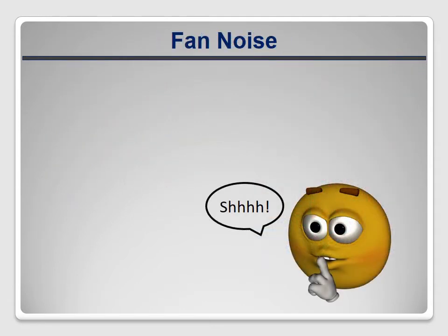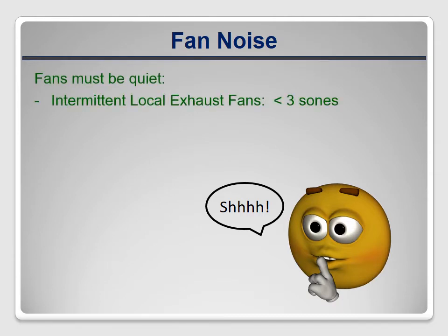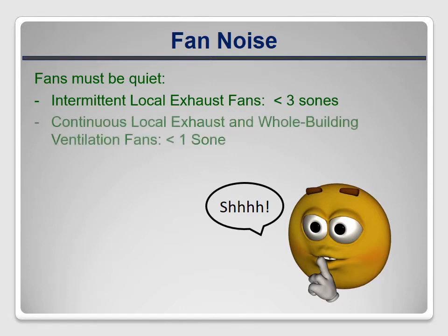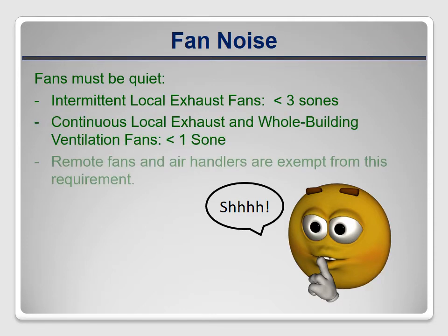The standard also requires that all fans run quietly. Intermittently operated exhaust fans must generate no more than three sones. That's not super quiet, but those fans are off most of the time. Continuously operated fans and whole building ventilation fans must be one sone or lower.